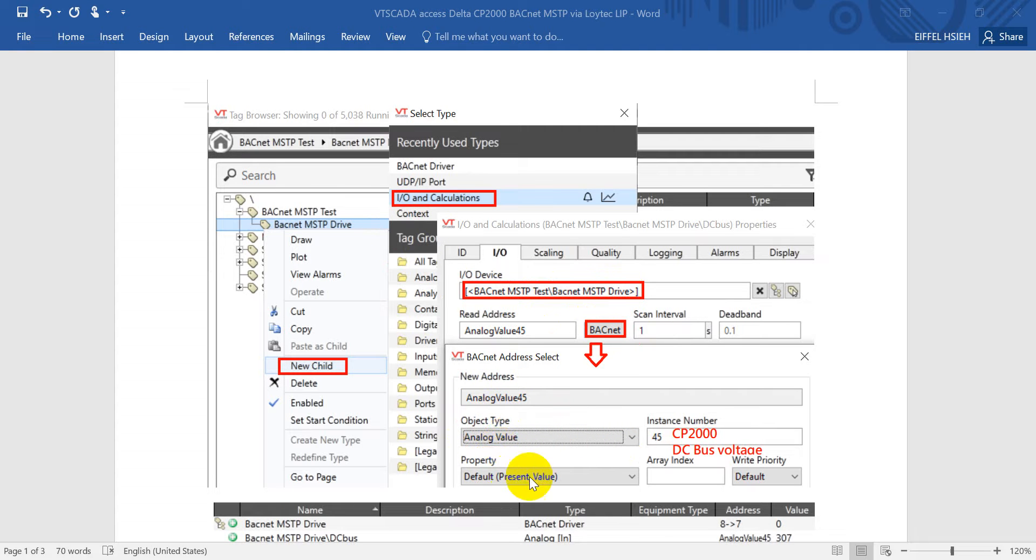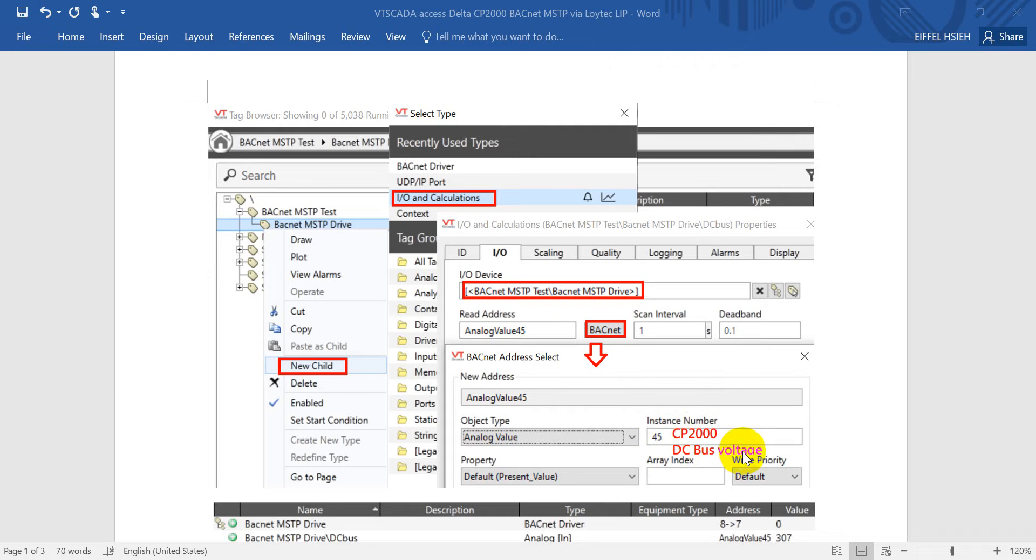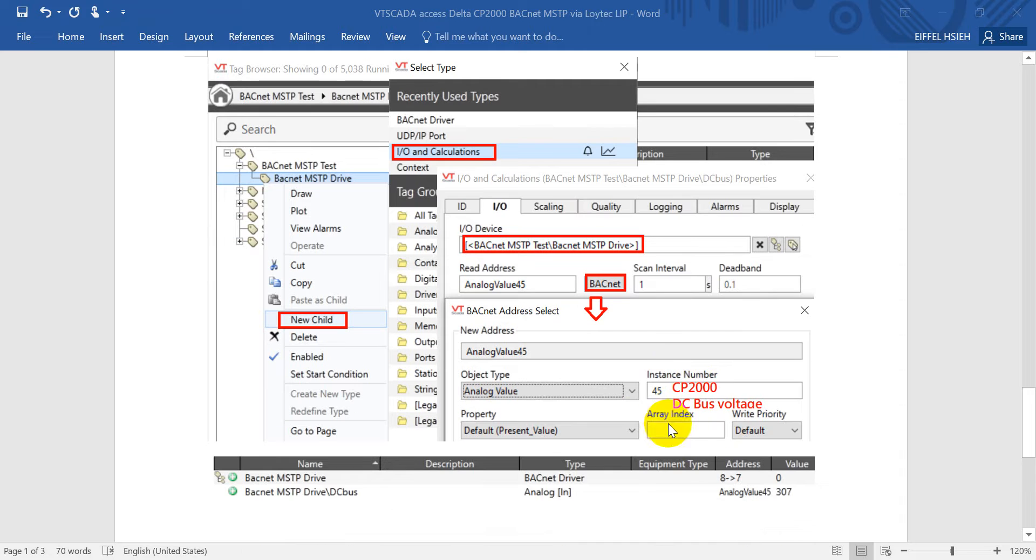Here the property - keep the present value. We assign our instance number as 45. That means the CP2000 DC bus value. After we click this one and click OK, apply, you can see this will show the DC bus voltage of CP2000.